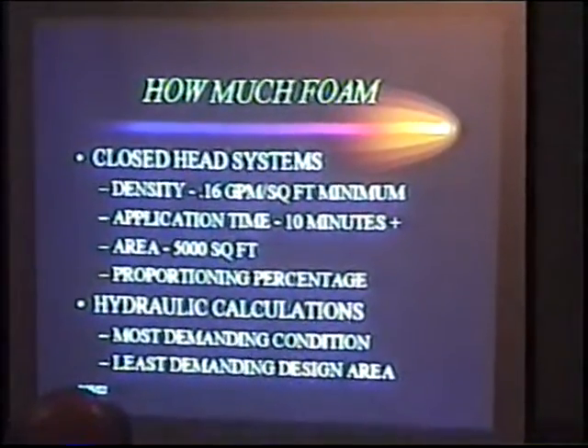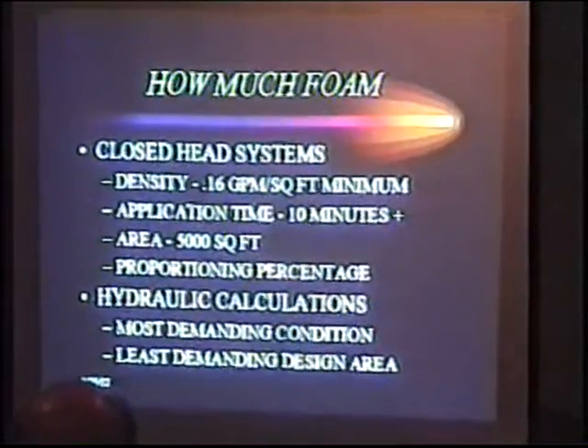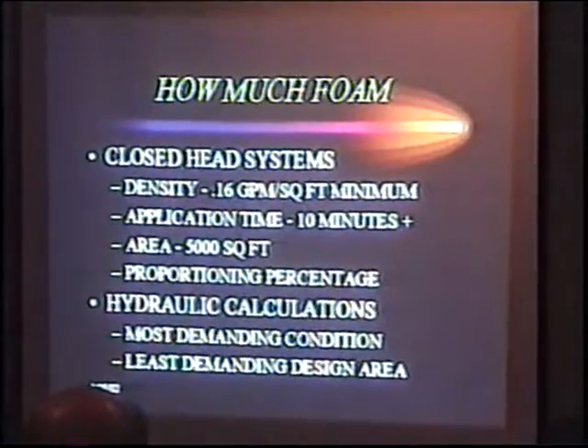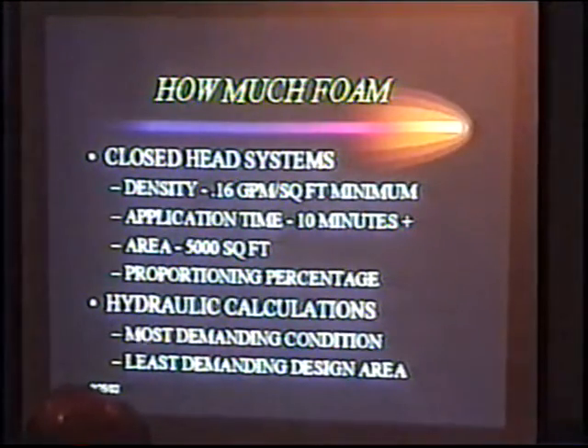How much foam? It's basically one rule of thumb: area times application time, times density, times the rate that you're proportioning. So it's roughly the size of your system. If you have a closed head system, the minimum is 0.16. But that doesn't mean it's not going to be higher. 0.25, 0.3, sometimes with the larger sprinkler systems, it's even more.